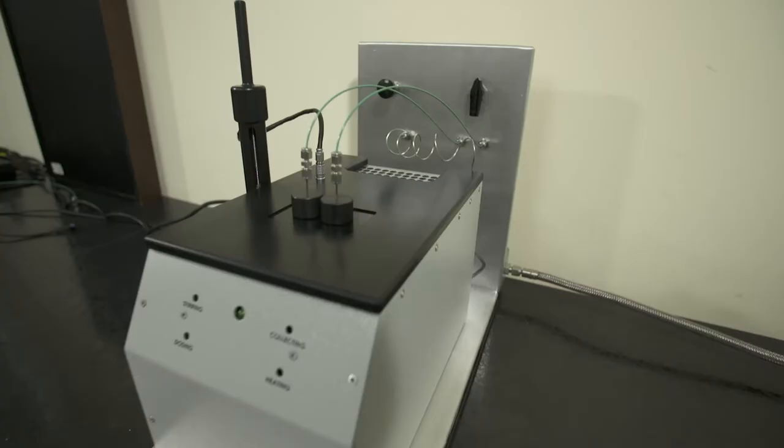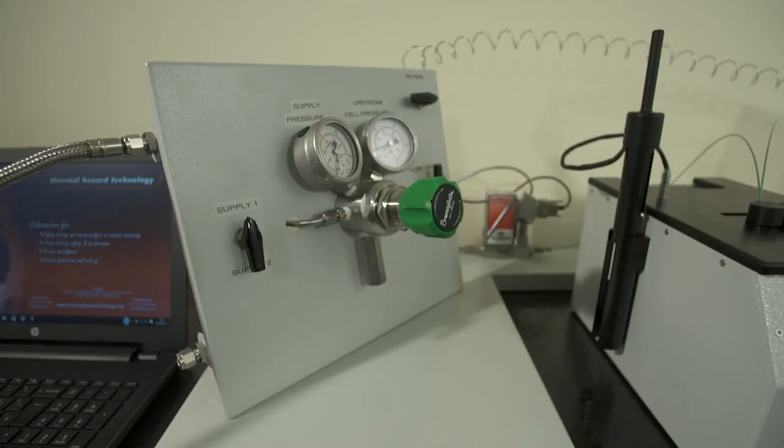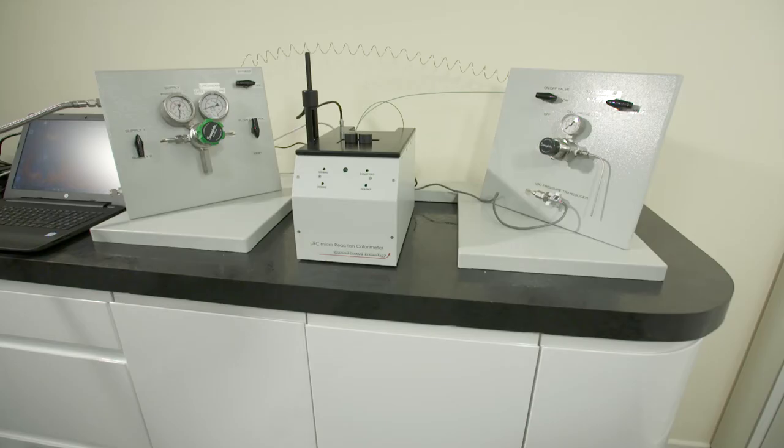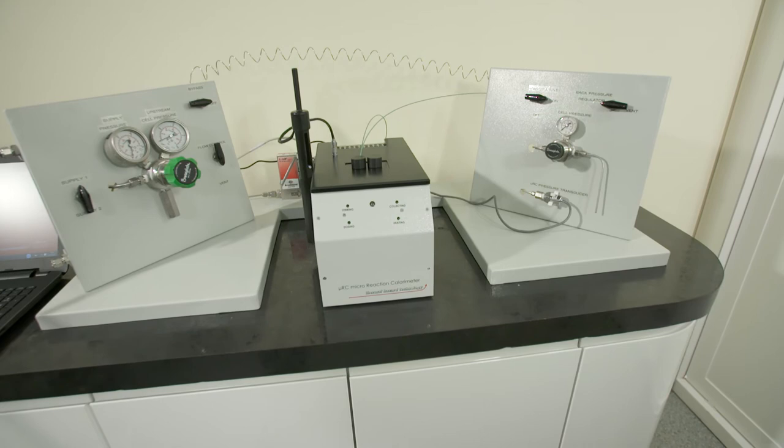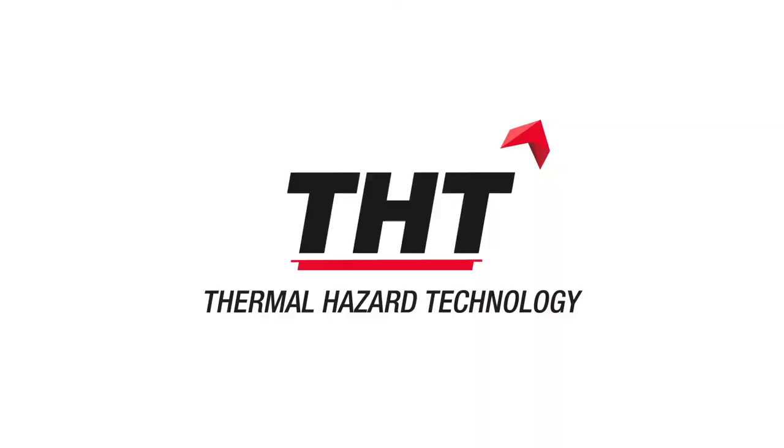The rig delivers the gas simultaneously to both the sample and reference cells. The gas flow option consists of a flow controller to regulate gas flow into the cell. This has been used to good effect to study carbon capture involving the exothermic reaction that occurs when CO2 gas is absorbed by an amine solution.